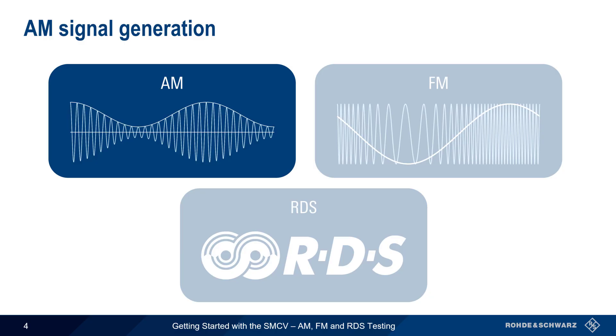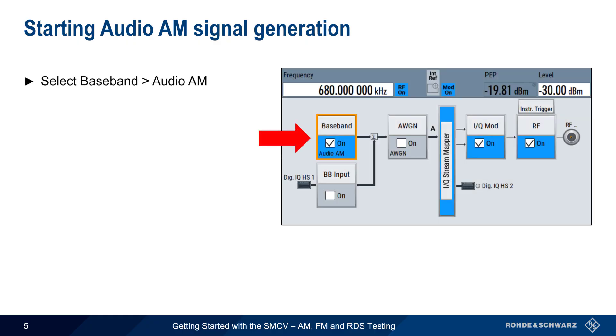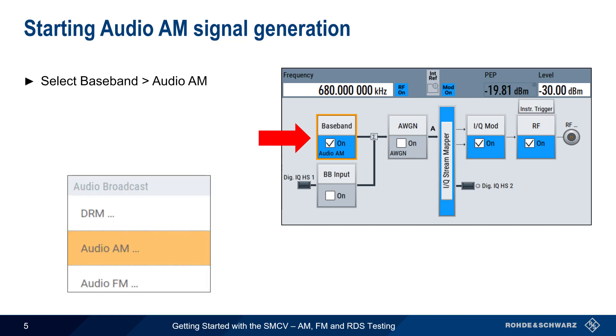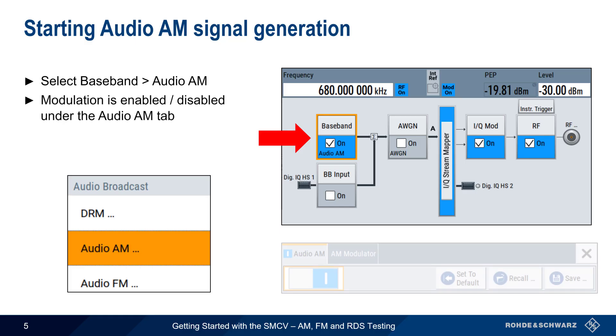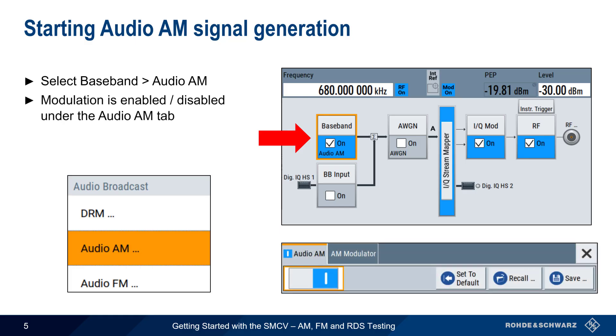The first of the three sections of this presentation covers analog AM signal generation. The first step is to go to the Baseband block in the SMCV's user interface and select Audio AM from the list of available modulation types. Clicking on this block will bring up the Audio AM dialog, and a simple toggle switch is then used to enable or disable AM audio modulation.